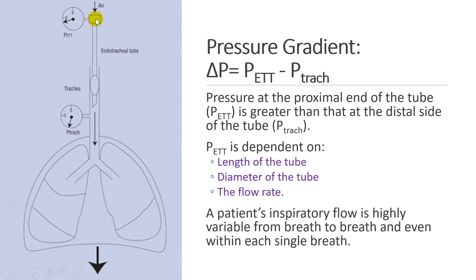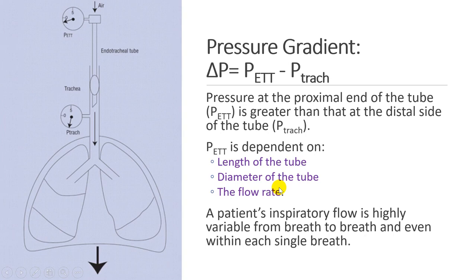If you measure the pressure at the proximal end of the tube and the pressure at the distal end of the tube, you get a difference between these two pressures. This is what the machine tracks, and this pressure difference is used to deliver a pressure support equal to that difference. The endotracheal tube pressure depends on the length and diameter of the tube and the flow rate. While length and diameter are fixed, the flow rate is highly variable from breath to breath and even within each single breath.